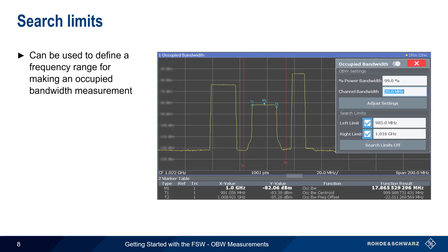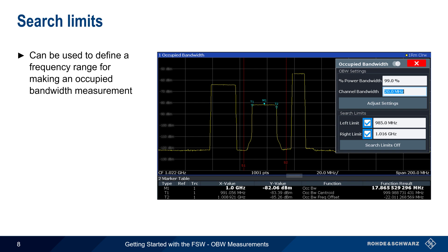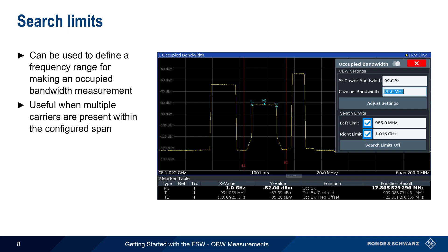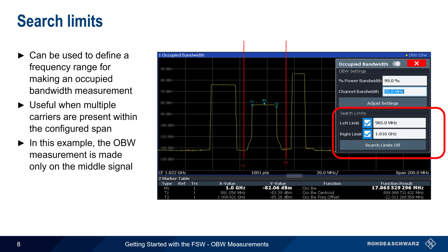An additional useful feature is Search Limits, which can be used to define the frequency range over which the occupied bandwidth measurement is made. This is useful when the configured span contains multiple carriers, only one of whose occupied bandwidth is to be measured. In this example, we've enabled both left and right search limits, so the FSW will only measure the occupied bandwidth of the signal in the middle of the defined span.